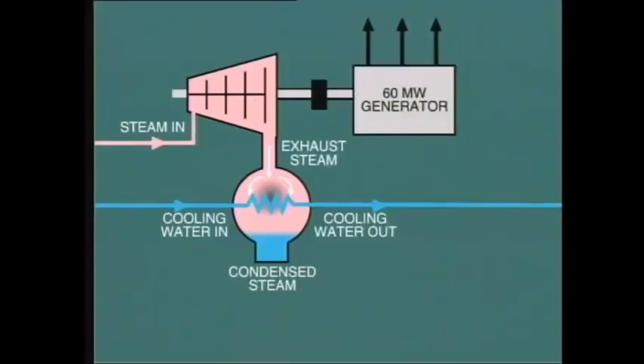As we already pointed out in an earlier module, a vacuum is formed when steam exhausting from the turbine is cooled and condensed back into water. The dramatic change in volume from steam to water leaves a large empty space, and as the condenser is a closed vessel, the result is a vacuum. The actual pressure in the steam space of the condenser and correspondingly at the turbine exhaust will be about 1 to 2 psia, depending on actual local conditions.